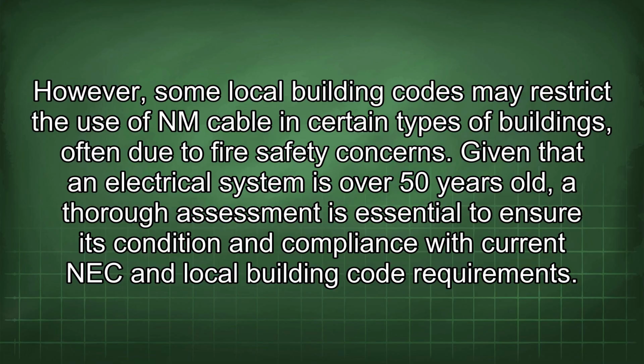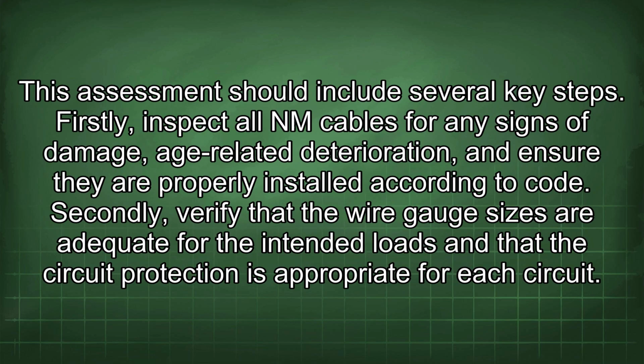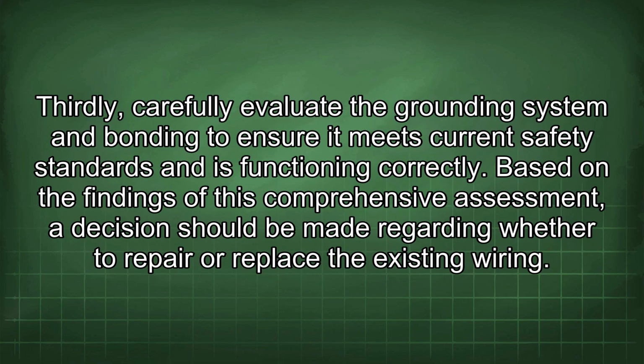fire safety concerns. Given that an electrical system is over 50 years old, a thorough assessment is essential to ensure its condition and compliance with current NEC and local building code requirements. This assessment should include several key steps. Firstly, inspect all NM cables for any signs of damage, age-related deterioration, and ensure they are properly installed according to code. Secondly, verify that the wire gauge sizes are adequate for the intended loads and that the circuit protection is appropriate for each circuit.